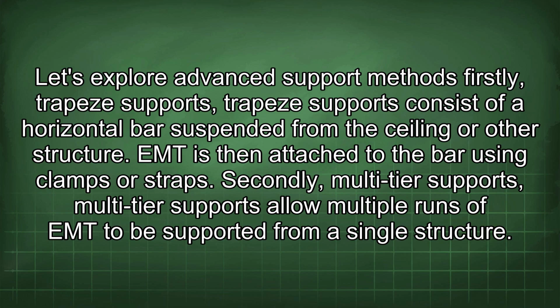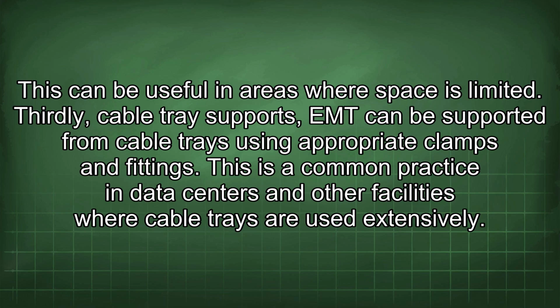Firstly, trapeze supports. Trapeze supports consist of a horizontal bar suspended from the ceiling or other structure. EMT is then attached to the bar using clamps or straps. Secondly, multi-tier supports. Multi-tier supports allow multiple runs of EMT to be supported from a single structure. This can be useful in areas where space is limited.